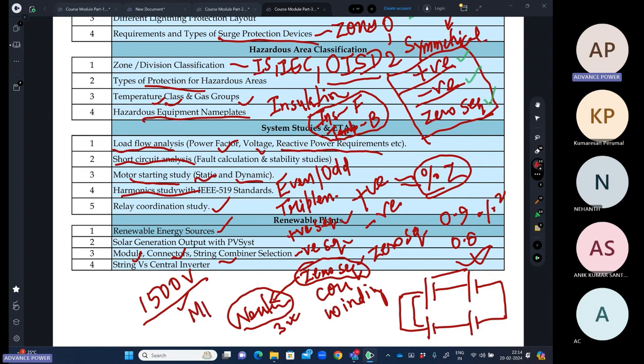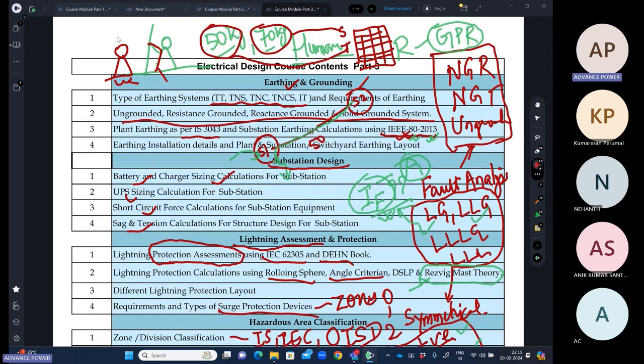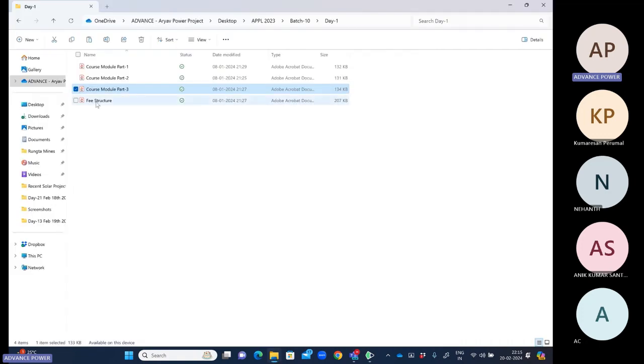We'll discuss about the MPPT of the module, the open circuit voltage and short circuit current of the module. So all those phenomena we'll discuss. We'll select the size of the fuse, cable selection. We'll select the combiner box, number of inputs required, then inverter, sizing of cable, and further the inverter duty transformer we'll discuss. We'll discuss difference between the string and central inverters also, where we are using and how it is giving the advantage in different sizes of the plots we are getting in the solar parks or any other places.